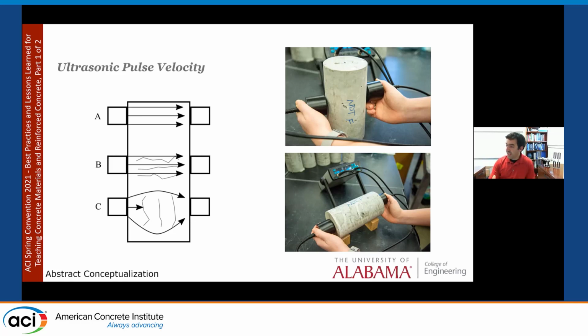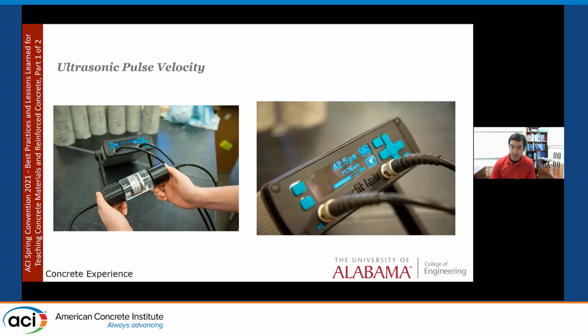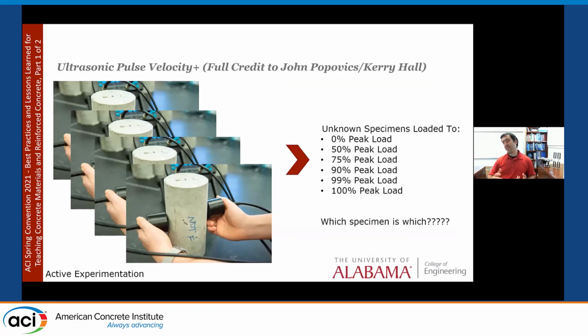So you teach that. Again, you're going to teach them the theory of this. They go into lab, they measure a known cylinder, and they can also practice, and I mentioned this in the document, they can practice the calibration process. This is also sometimes overlooked because, well, laboratory equipment can go out of calibration. You got low batteries or something, you know, so it's important to also teach that. And then we come again to the experiential part.